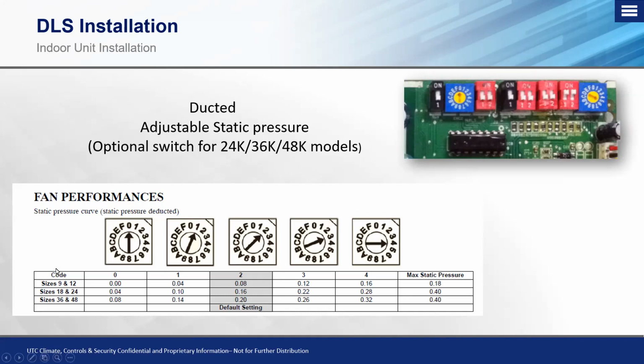So for example, on the sizes 9 and 12,000 BTUs, our default setting is 0.08 inches of static pressure. It's really not much, and these units are typically designed as a straight shot and cannot facilitate multiple takeoffs or multiple rooms to condition just because of the minimum static pressure that we have. Now you can see if you adjusted this to the maximum on there, you're only dealing with just about 0.2 inches of static pressure, which isn't much at all. Again, smaller units such as the 9 and 12 are geared towards more of a one-to-one application as far as ducting is concerned. We really can't facilitate any takeoffs on there and be able to provide the correct amount of CFM to that space.